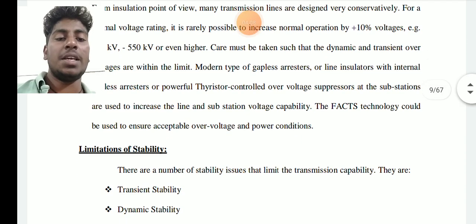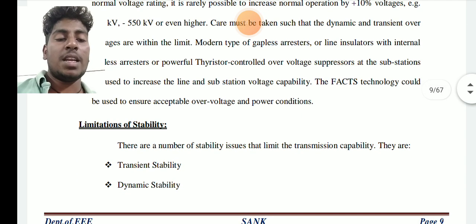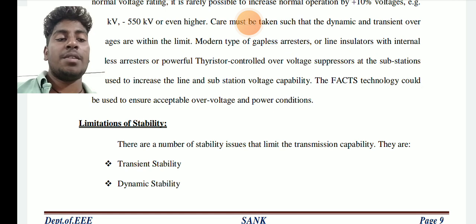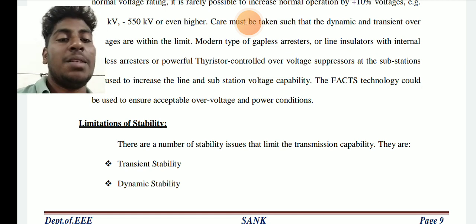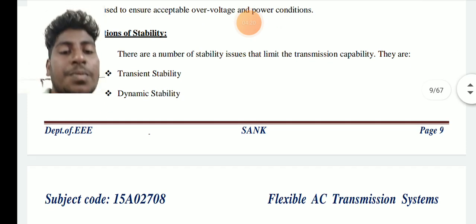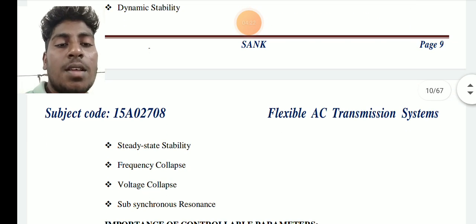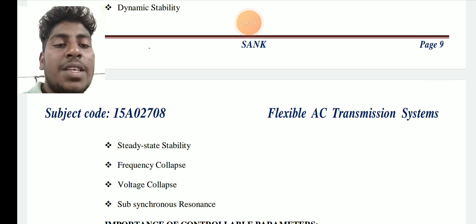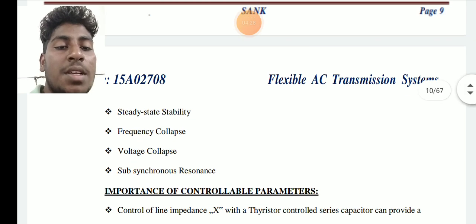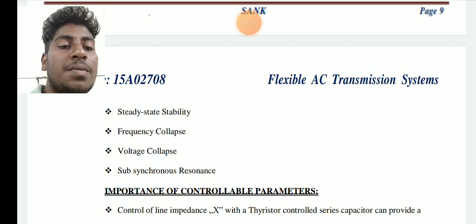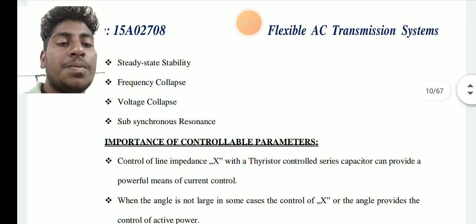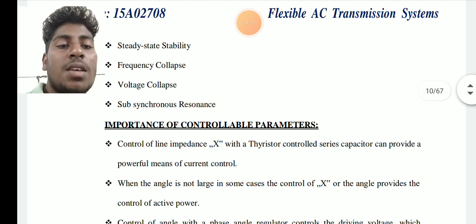Limitations of stability. There are a number of stability issues that limit transmission capability. There are transient stability and dynamic stability, two types; steady state stability, frequency collapse, voltage collapse, subsynchronous resonance. Importance of controllable parameters.